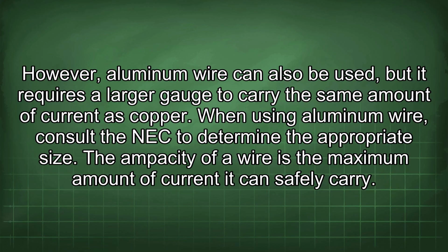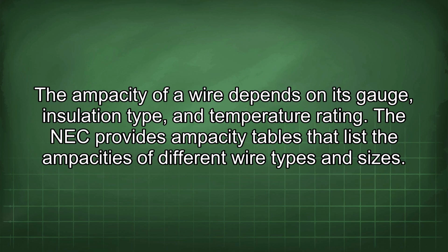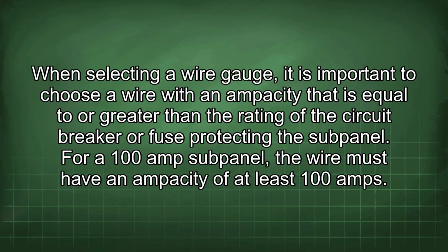The ampacity of a wire is the maximum amount of current it can safely carry. The ampacity of a wire depends on its gauge, insulation type, and temperature rating. The NEC provides ampacity tables that list the ampacities of different wire types and sizes. When selecting a wire gauge, it is important to choose a wire with an ampacity that is equal to or greater than the rating of the circuit breaker or fuse protecting the subpanel. For a 100 amp subpanel, the wire must have an ampacity of at least 100 amps.